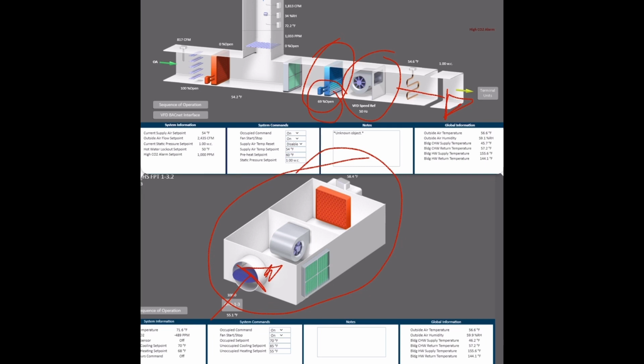And that's how you provide cooling to a specific room or area. That air goes through down there, and then it goes through your fan, and then it goes outside to your supply or your vent on the VAV box. If you see in the VAV box, that's where you have your damper, and that's where your air goes through. Hopefully you're having a better understanding of how this operates and how you provide cooling to those specific areas or to that specific room. One air handler will feed several rooms or a big area.